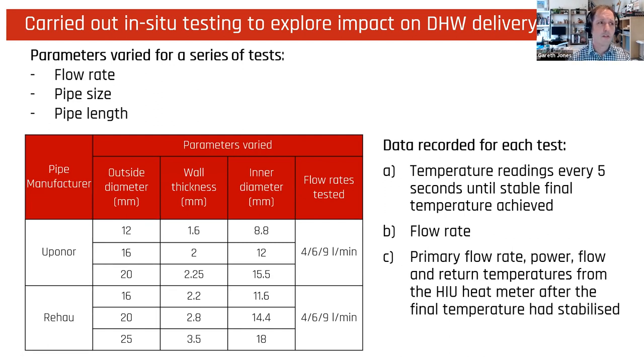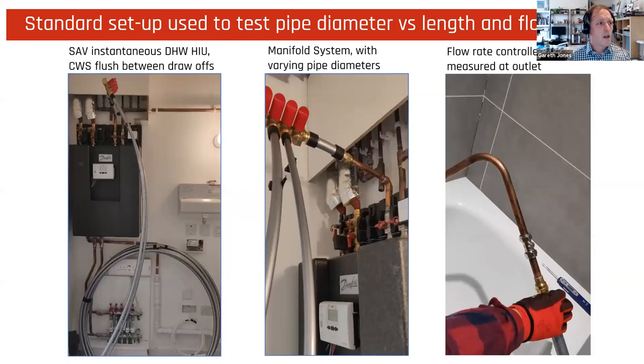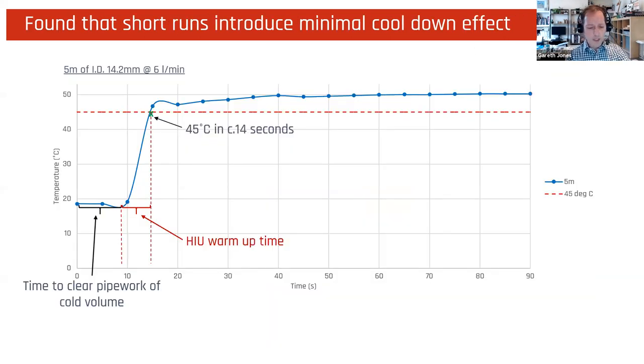We carried out in situ testing to explore the impact on domestic hot water delivery times. So we used a whole series of different pipe diameters. We used two different manifold systems. We varied flow rate, pipe size and pipe length. And we recorded temperature readings every 5 seconds until we got a stable temperature. And we looked at flow rate, and then we recorded a bunch of data for each test. We used a standard setup. So we've got pipe, we've got a manifold, and then we controlled flow rate at the outlet and measured temperatures. I think, again, I'm being signaled on time, so I'll try jumping on.